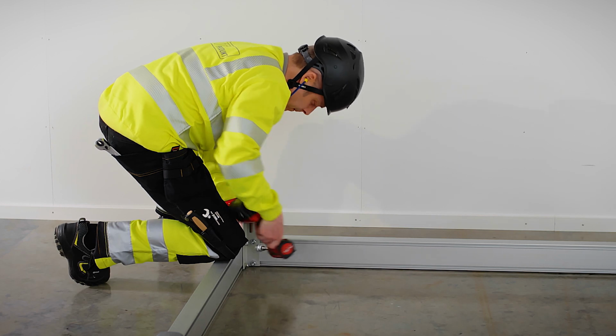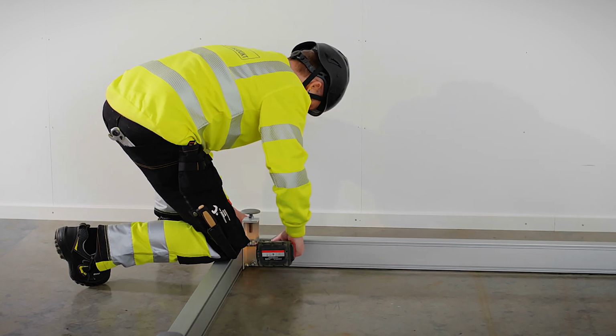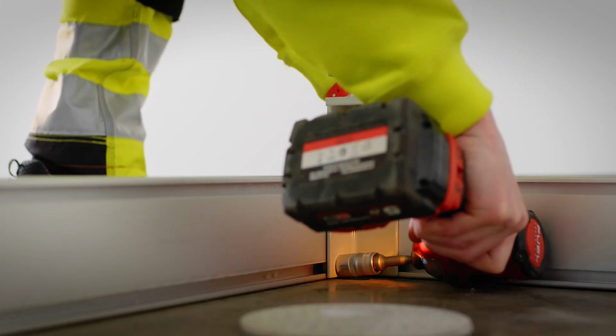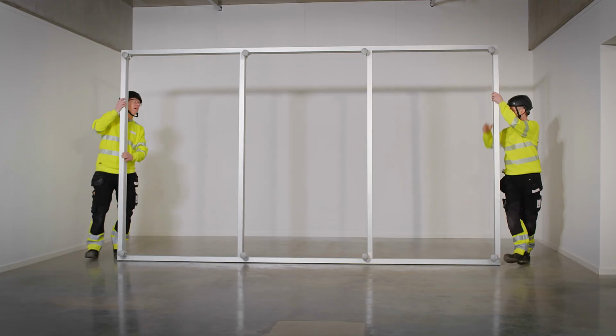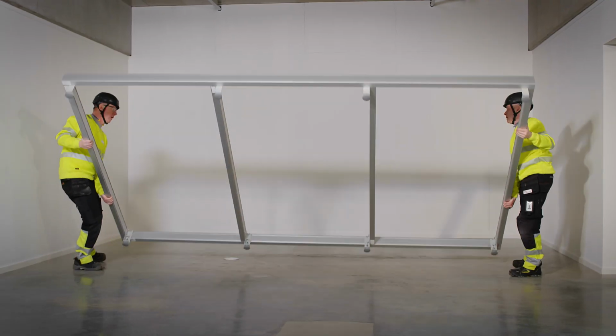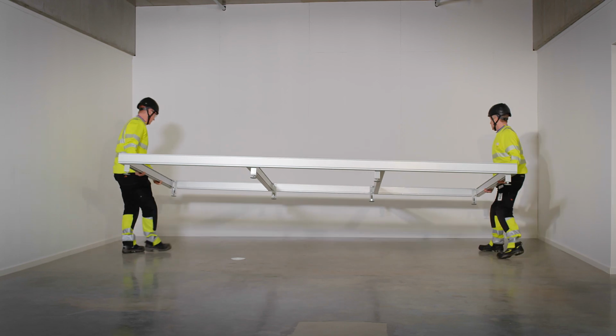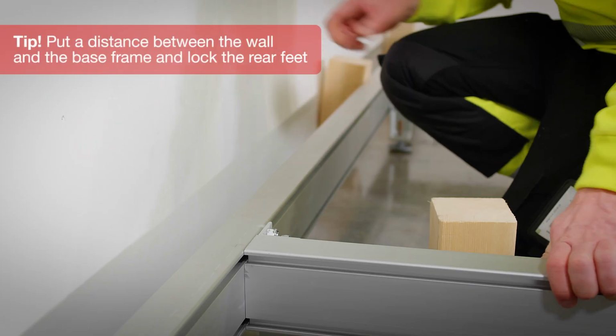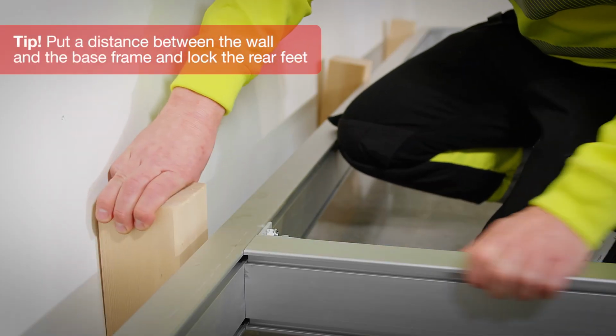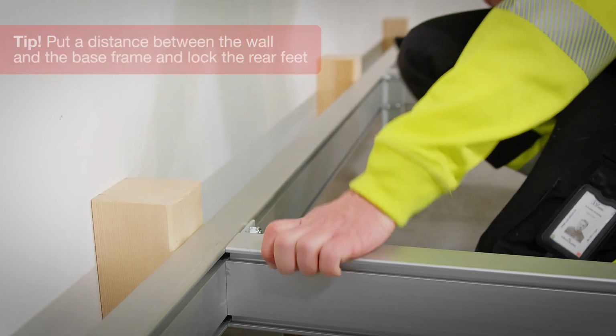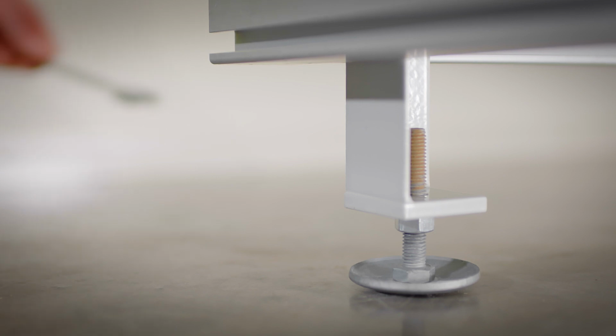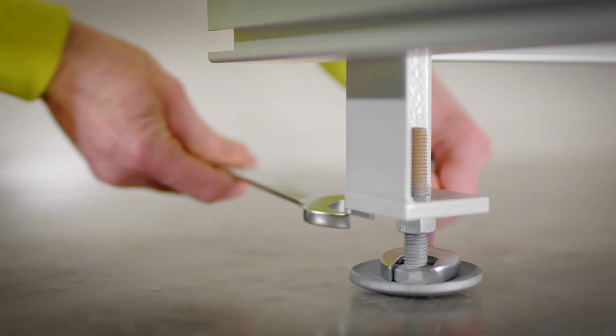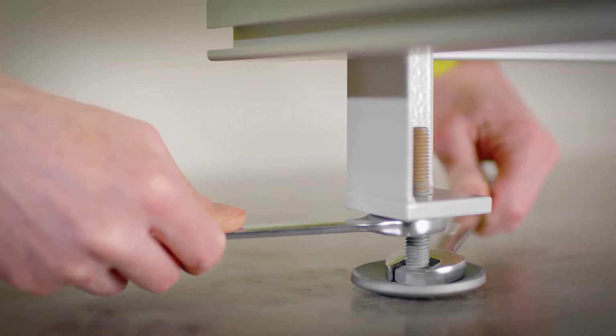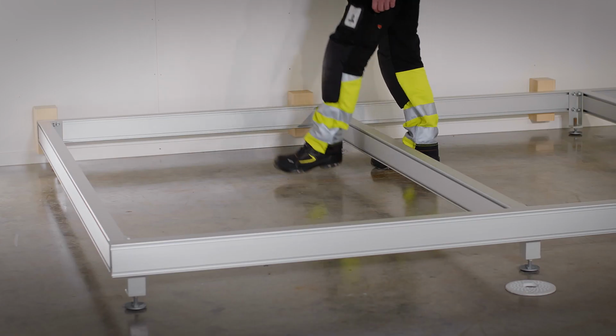The next step is to build the base frame. If the floor is level, it's advisable to build it upside down and then turn it over. You can put a distance between the base frame and the wall to prevent it from moving when sliding on the unit sections. Make sure the unit is level by adjusting the feet. The nut and foot must be turned in the right direction. Lock the rear feet as they will be difficult to access later.